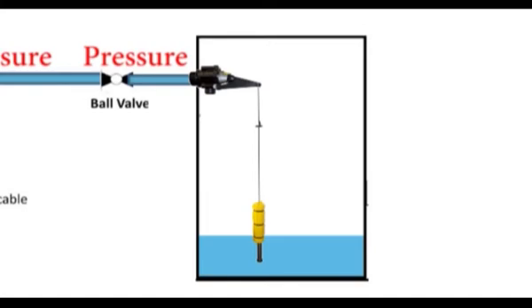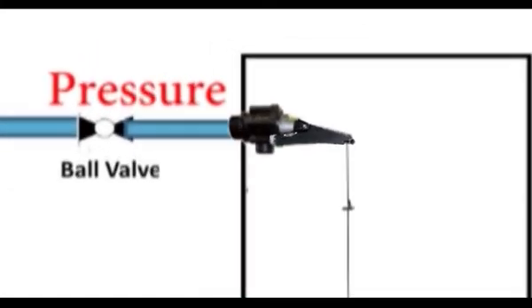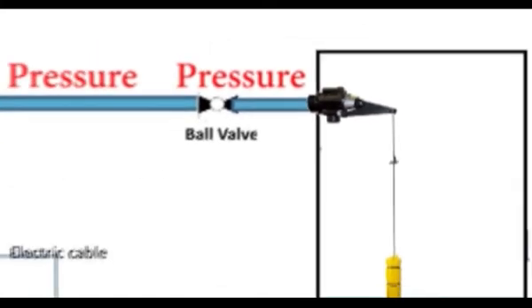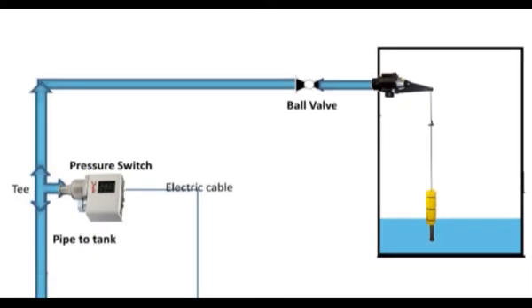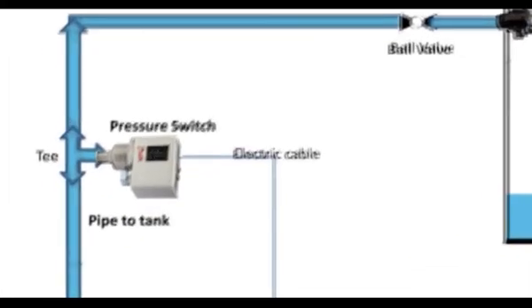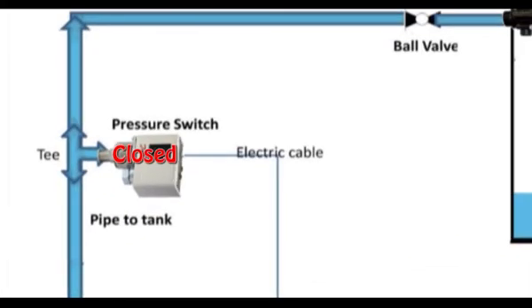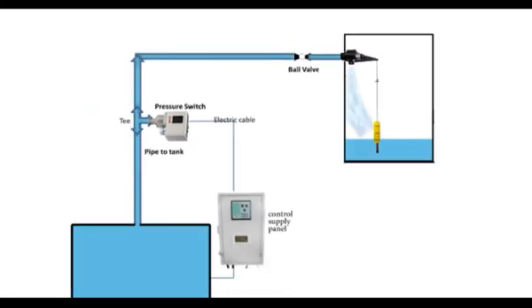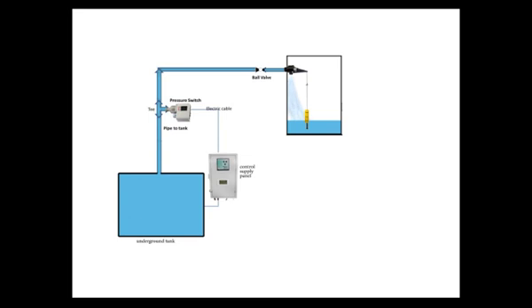Weight of same will turn on the differential float valve. As valve opens, pressure in pipeline will get reduced. Due to reduced pressure, pressure switch contact will be changed to close condition and due to same pump will start again. This cycle will continue.